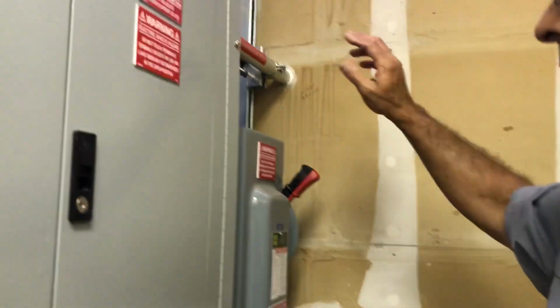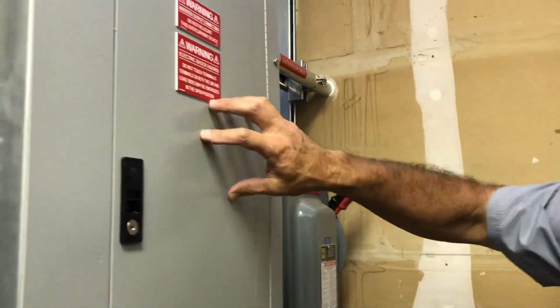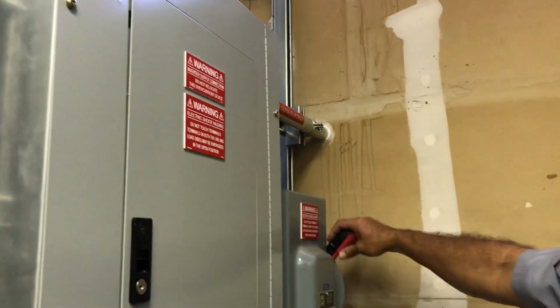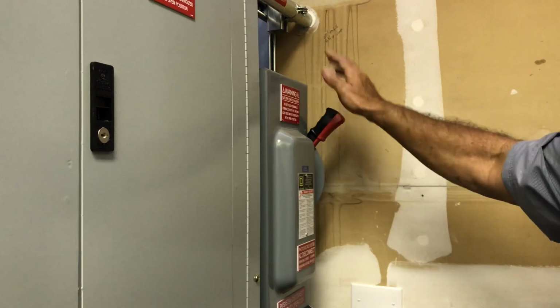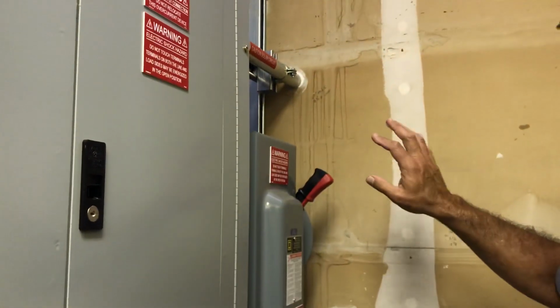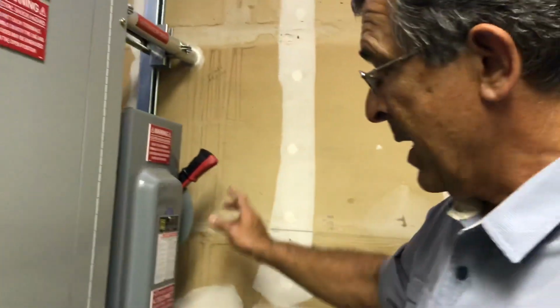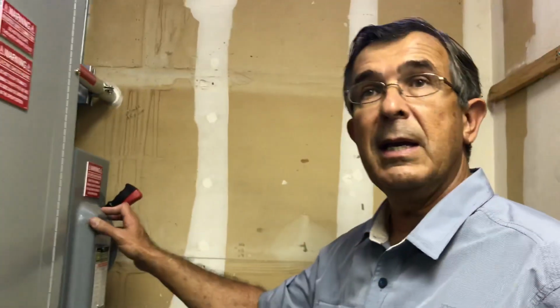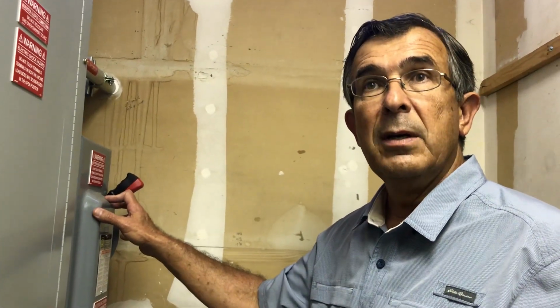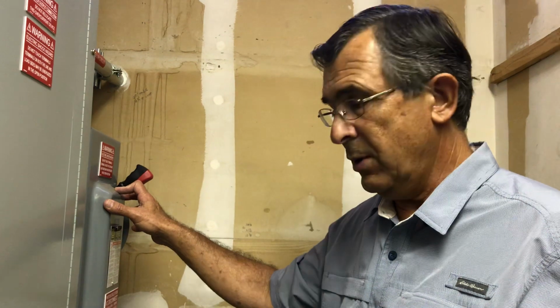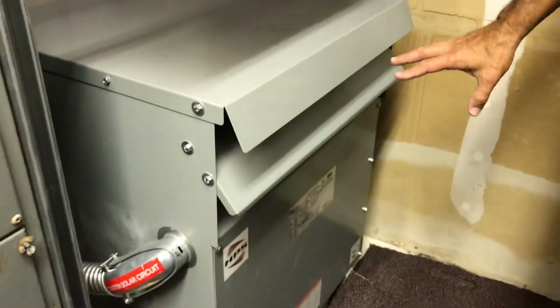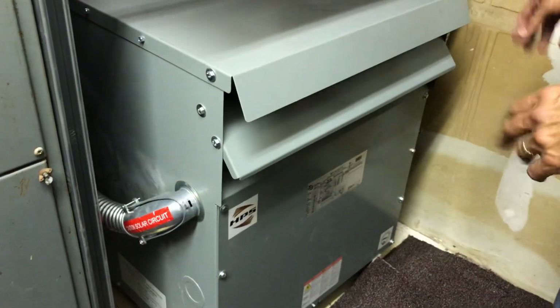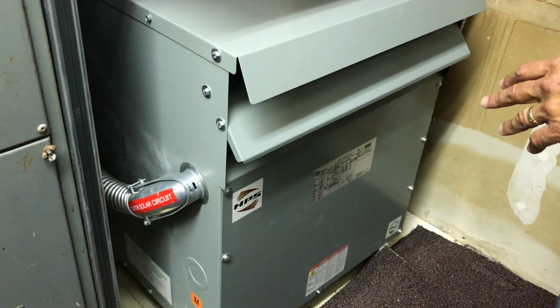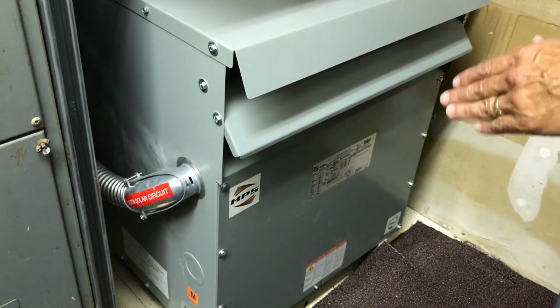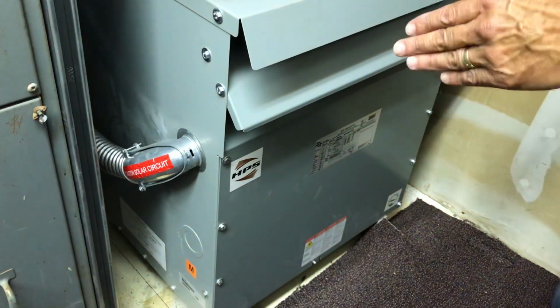So now let's get back to this. We've brought that electricity in here. We've now combined it into a 100 amp circuit. We're now going to send it to our disconnect, which allows us to safely disconnect everything from each other. We now have to convert that electricity into the 208 volt 3-phase power that the church uses. We do that by running it through a transformer. And this transformer goes ahead and does what's called phase changing. It takes the 480 volt 3-phase power and converts it to 208 volt 3-phase power.